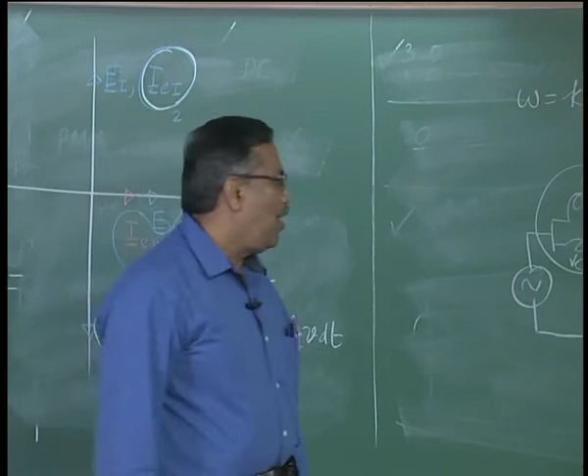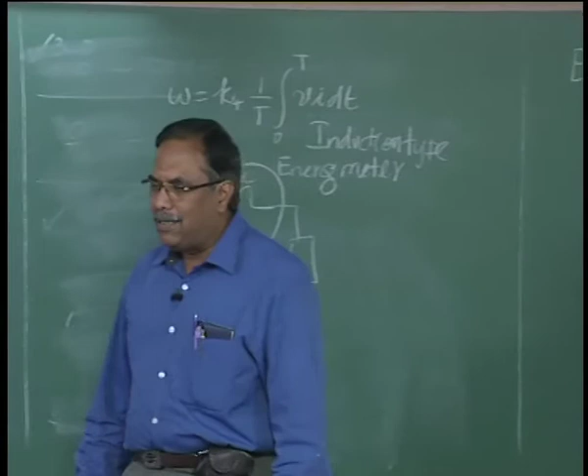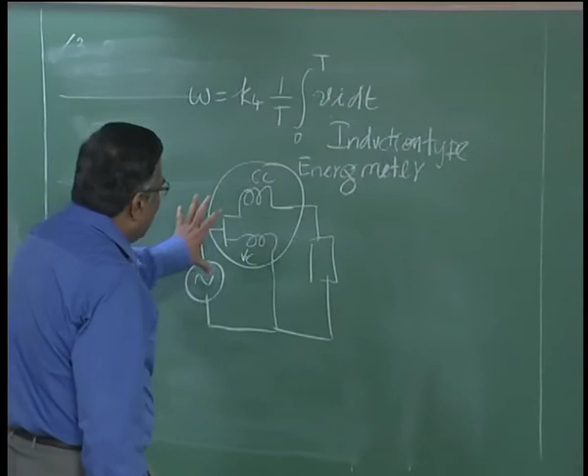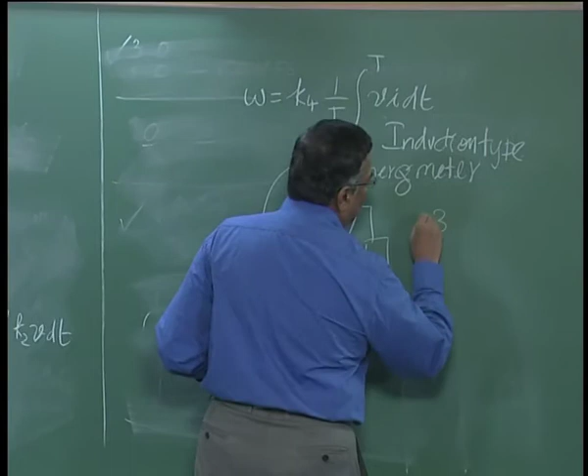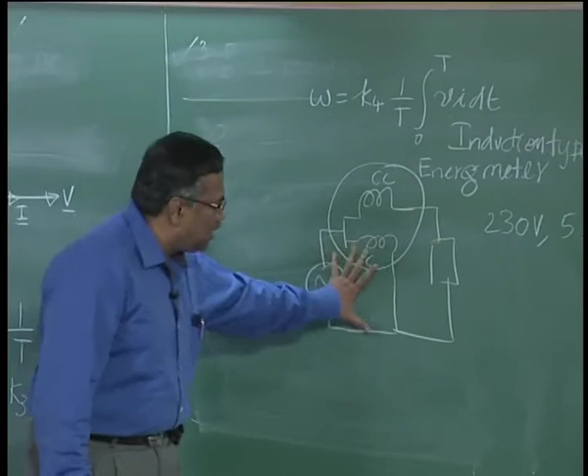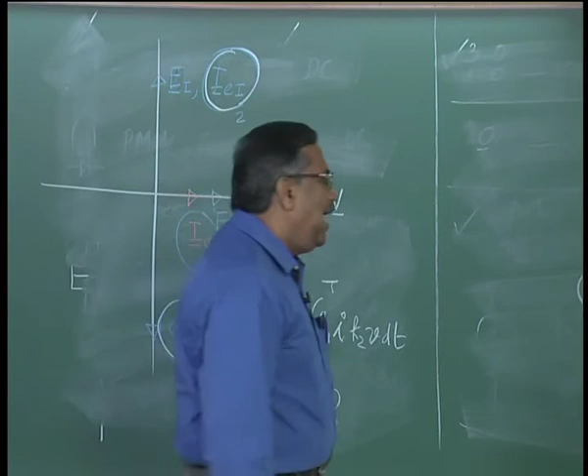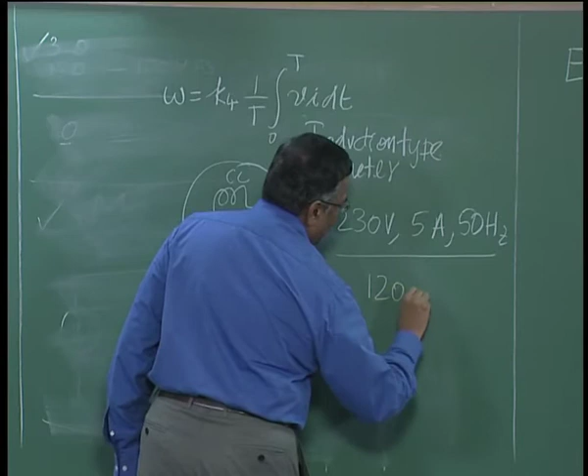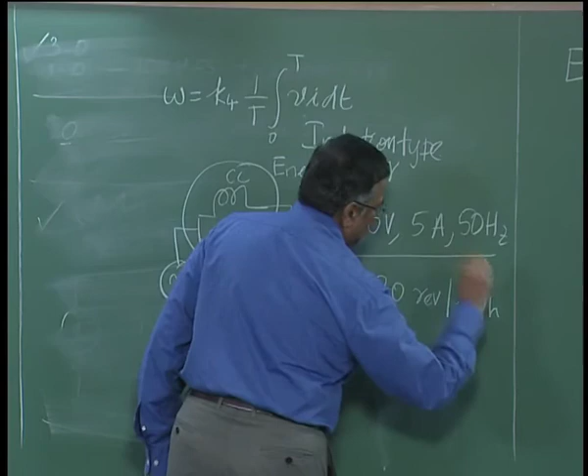So the final output is a count, and this count reflects the energy, in terms of units of electrical energy, 3600 kilojoules. If I look at a typical energy meter, it may be rated 230 volts, 5 amperes, 50 hertz, meaning I can apply 230 volts to the voltage coil, send a maximum of 5 amperes to the current coil, and the frequency it is designed for is 50 hertz. The last rating would be, say, 120 revolutions per kilowatt hour.